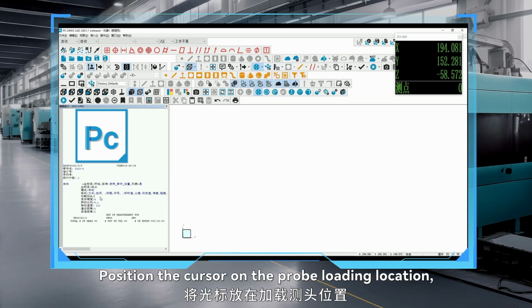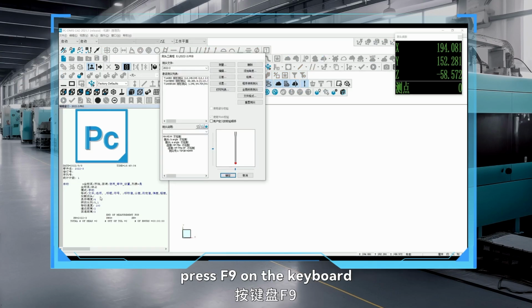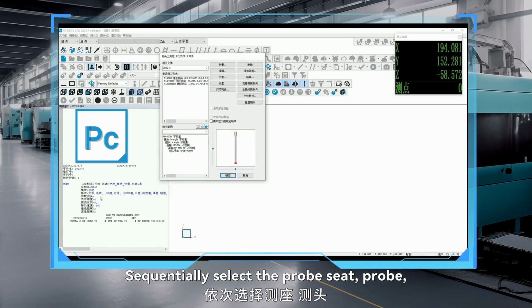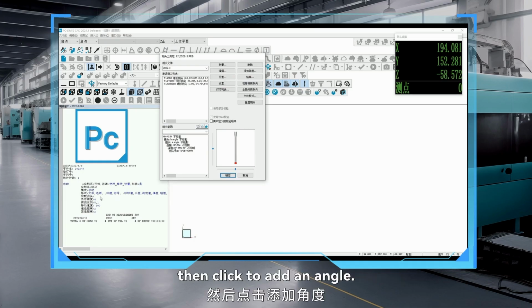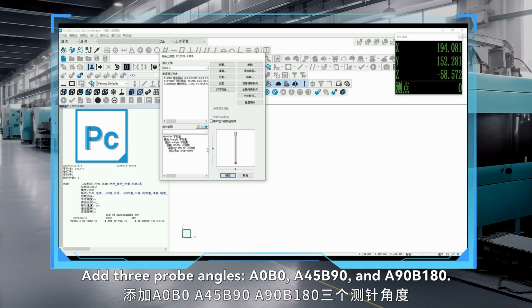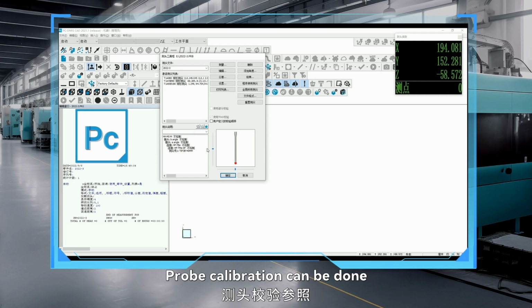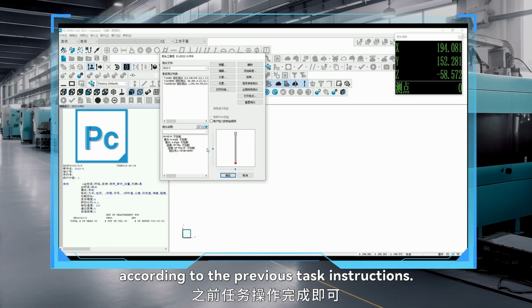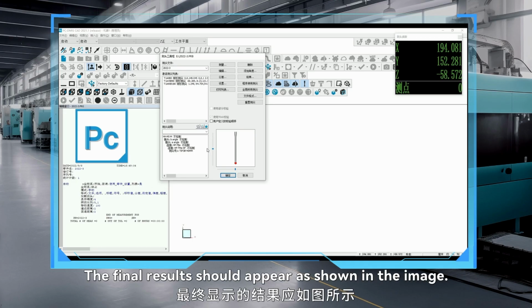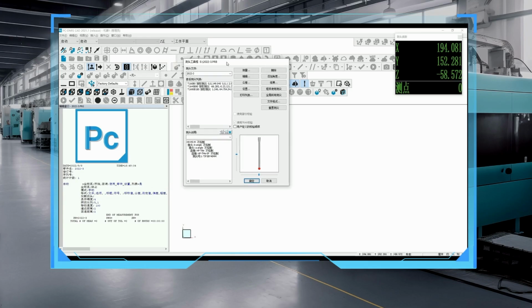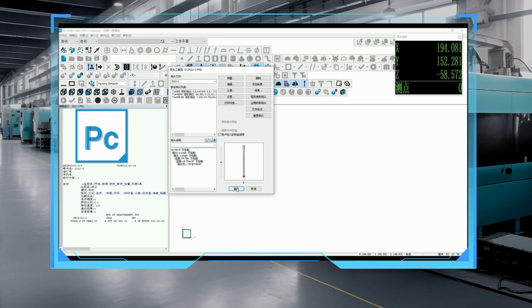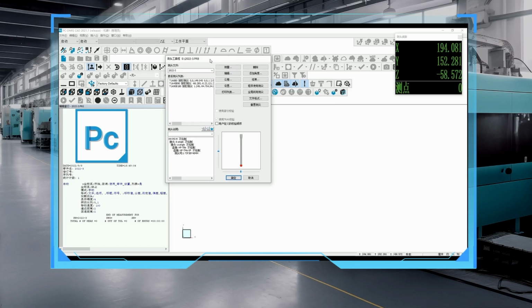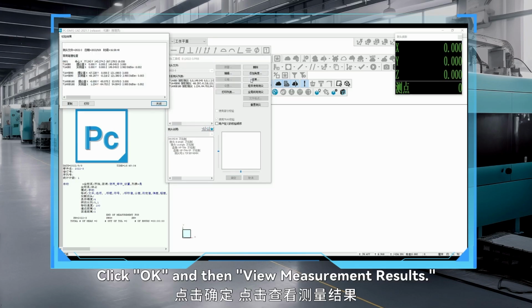Position the cursor on the probe loading location. Press F9 on the keyboard to enter the probe editing interface. Sequentially select the probe seat, probe, adapter, and CMM model. Then click to add an angle. Add 3 probe angles, A0B0, A45B90, and A90B180. Probe calibration can be done according to the previous task instructions. The final results should appear as shown in the image. Click OK, and then view measurement results.